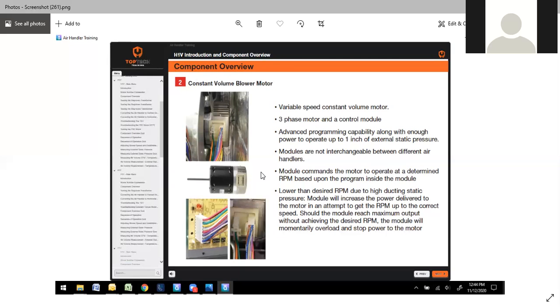If the RPM is lower than desired due to high static pressure, the module will increase the power delivered to the motor and attempt to get to that RPM and reach that correct speed. Should the module reach maximum output without achieving that desired RPM, the module will momentarily overload and stop power to the unit. There again, the static pressure is so important on these.